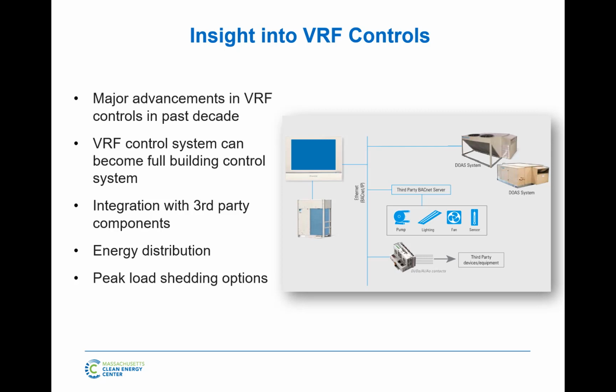All VRF BACnet, at least commercial VRF, is going to be over IP, just because of the amount of data that goes through it. MSTP would be a little limiting. So usually it's over IP. That's how we would do it. And there's a whole conversation about how to integrate BAS systems into VRF or VRF into BAS systems. The good news is if you had a water source heat pump job with 100 water source heat pumps in this building and you wanted to integrate those with BAS, a controls company would come in and say, okay, I've got to buy a little board and put it on each of those water source heat pumps.